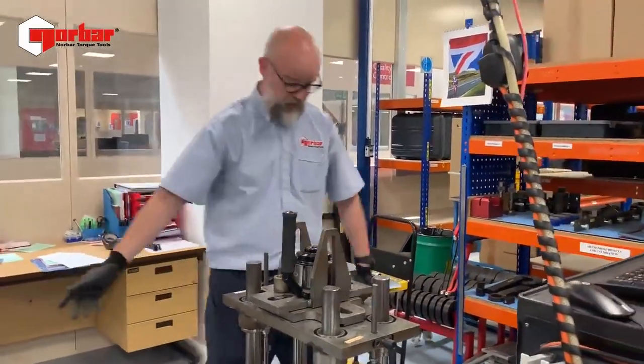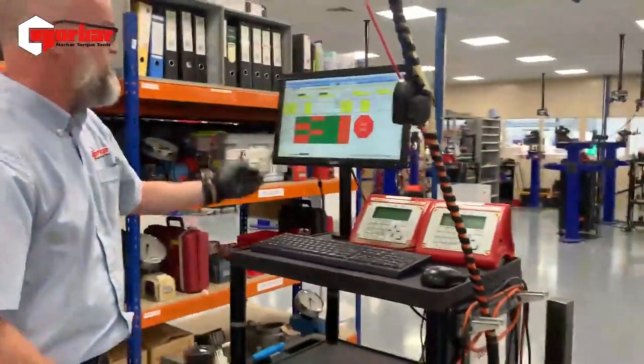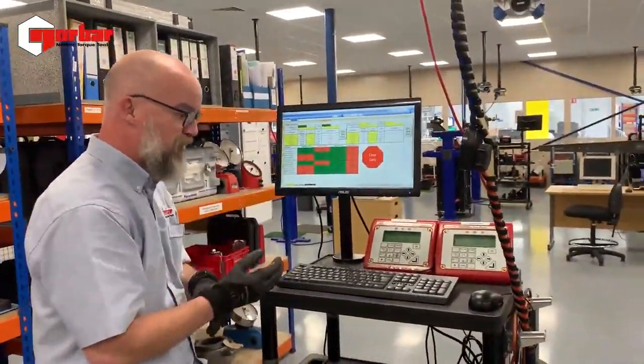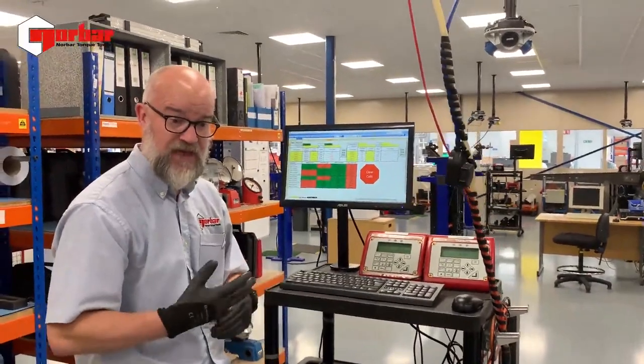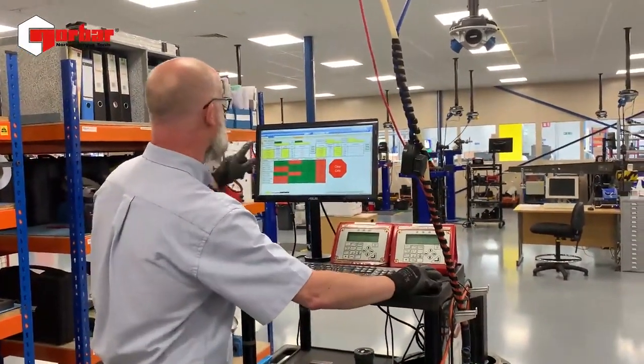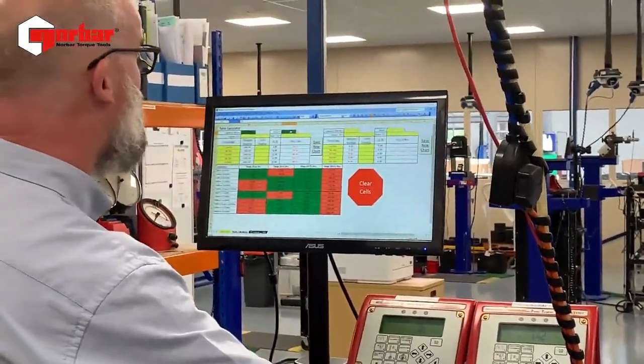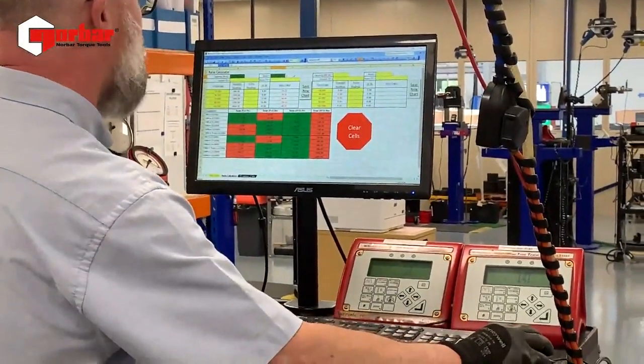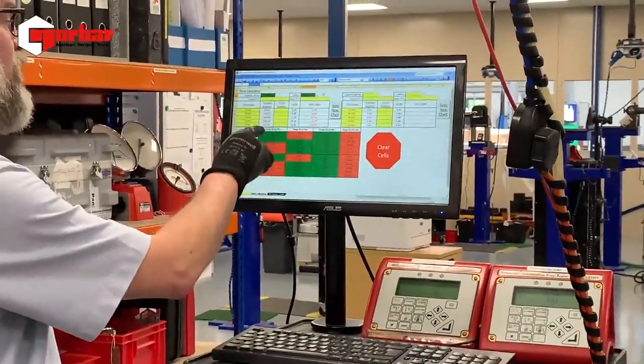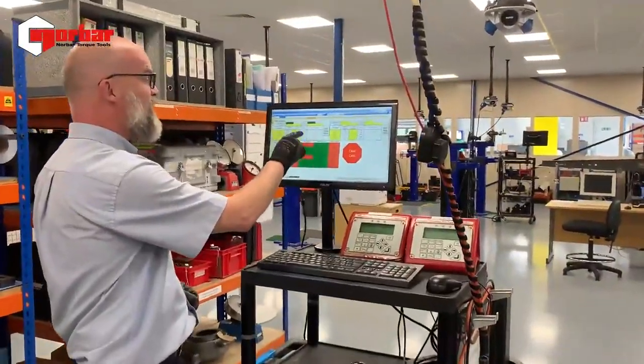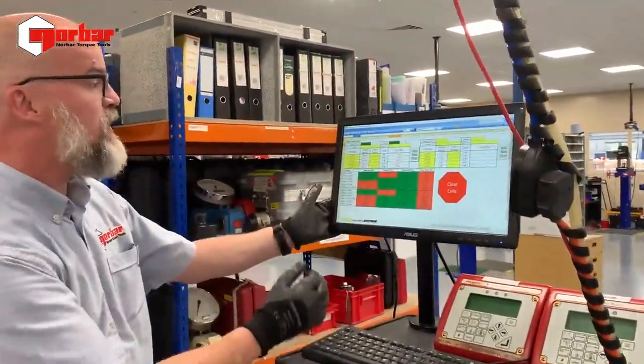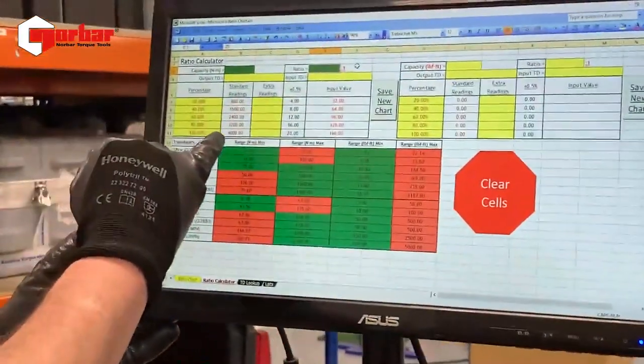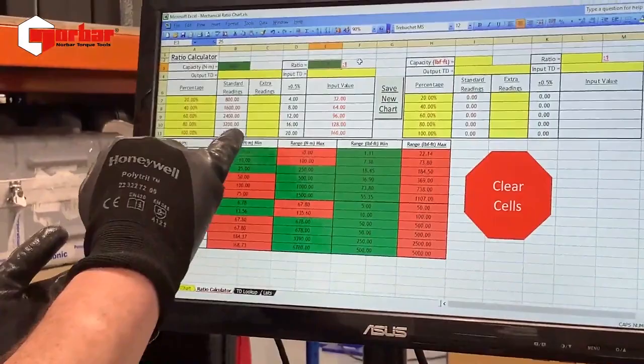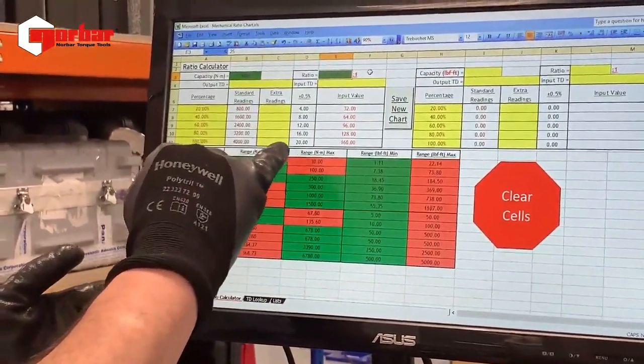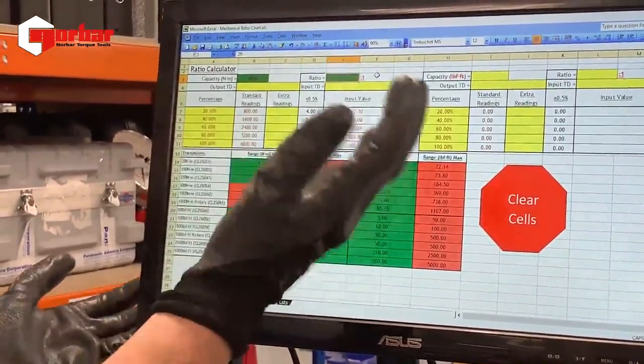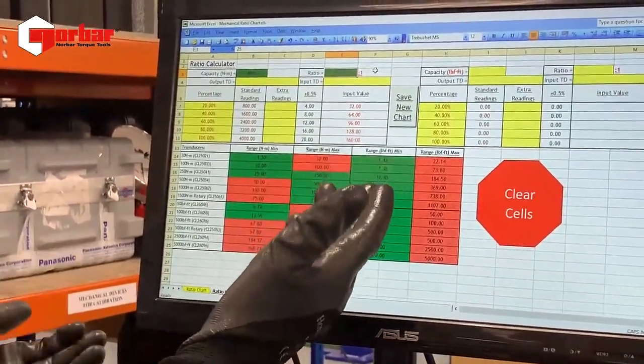At Norbar, we have a series of programs which we are not permitted to take out of the laboratory, but we can very quickly enter maximum capacity and nominal ratio, in this case 25:1, and we get output readings, input figures, and an allowable tolerance. So what we can see here, for example, at full scale we've got 4,000 Newton meters, and we allow basically a tolerance on our input TD of 20 Newton meters, nominal input 1,600.